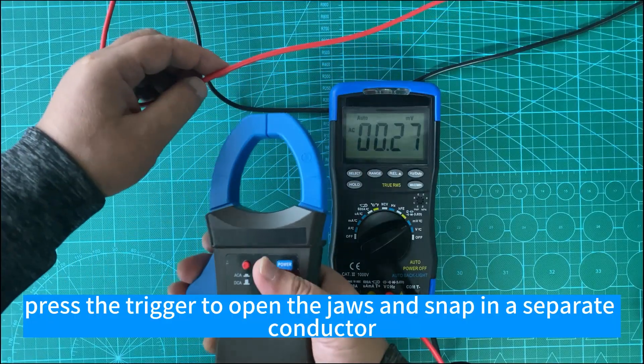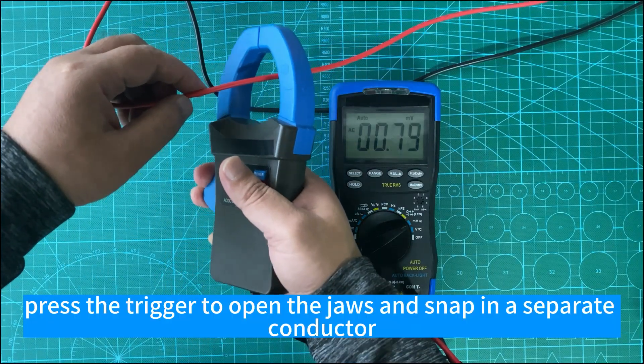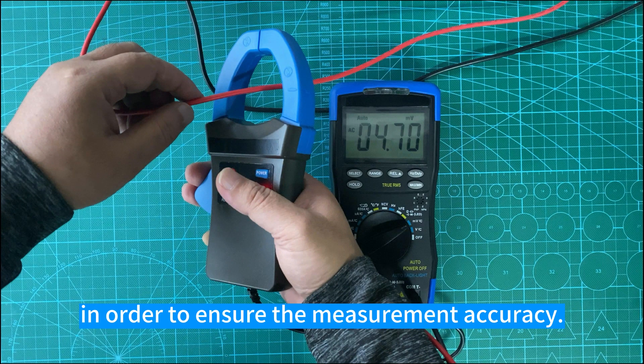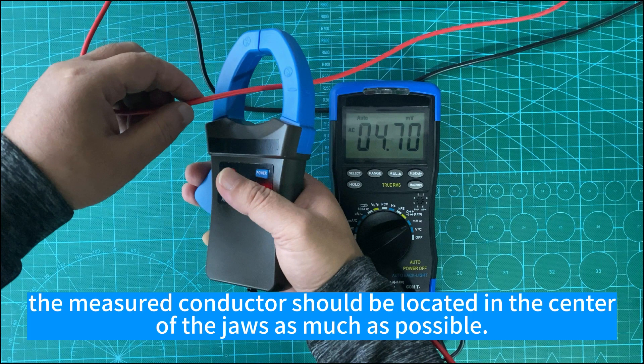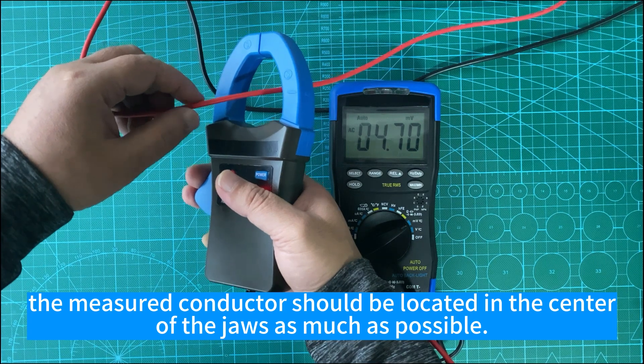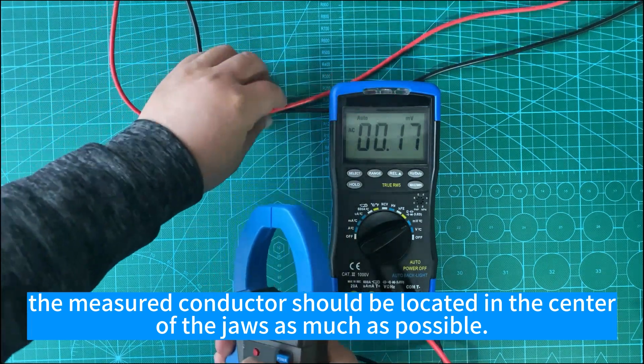Press the trigger to open the jaws and snap in a separate conductor. In order to ensure the measurement accuracy, the measured conductor should be located in the center of the jaws as much as possible.